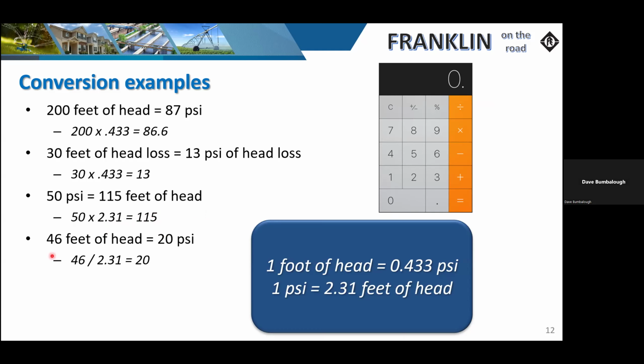If we were to take 46 feet of head, it's equivalent to basically 20 psi. With a calculator, you're just taking 46 divided by 2.31, and I can assure you that's like 19.9. So we round that up to 20.